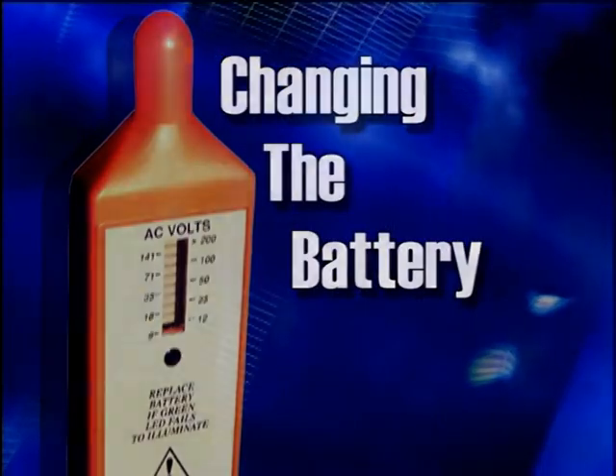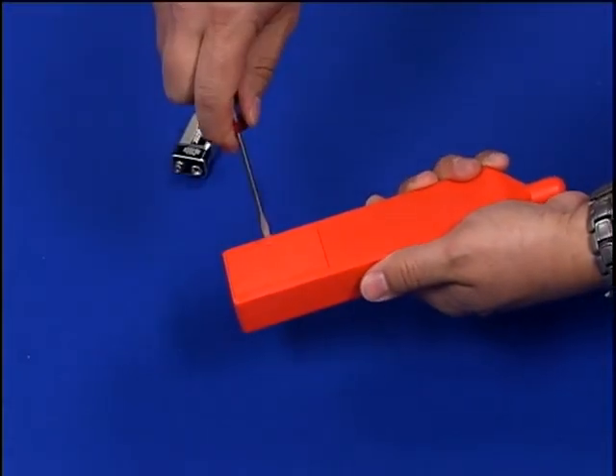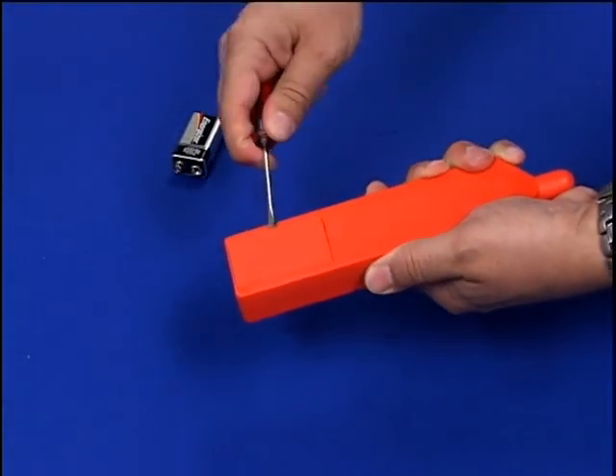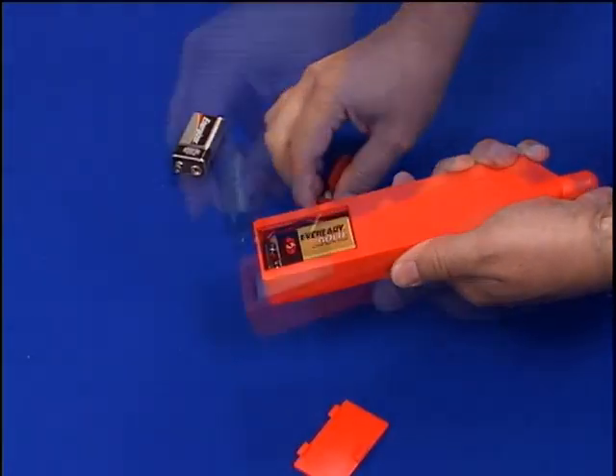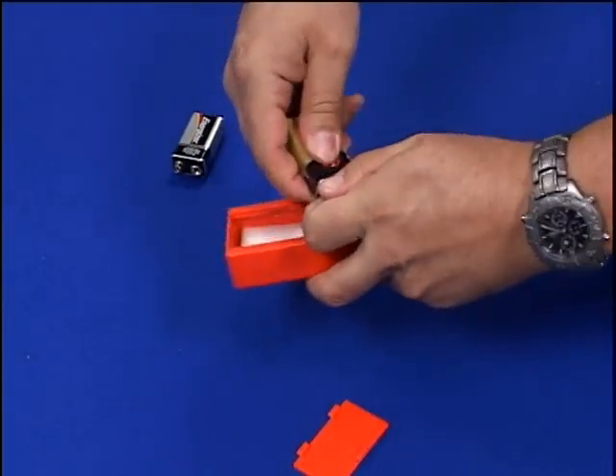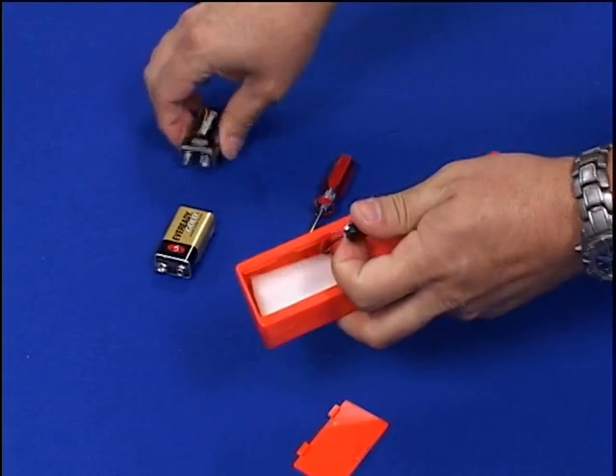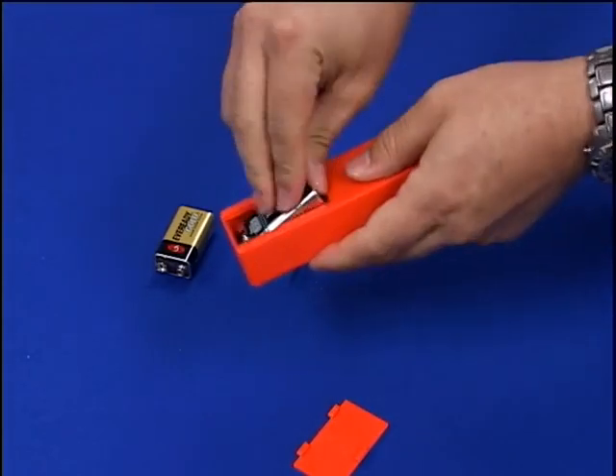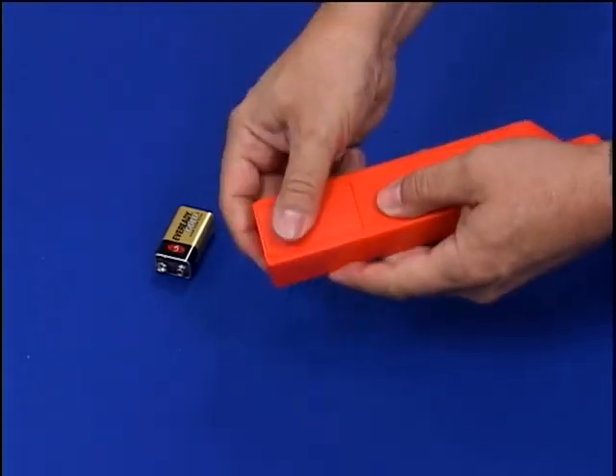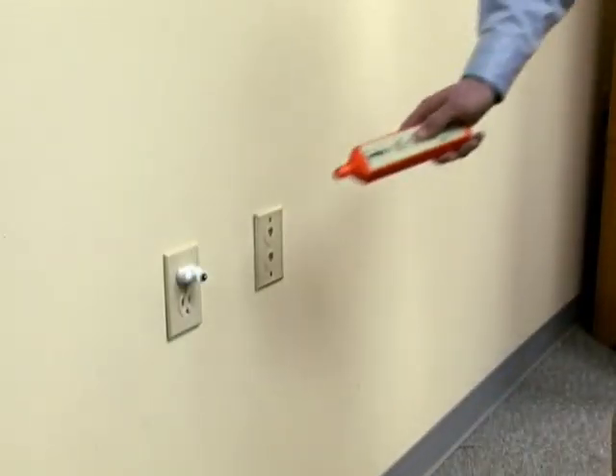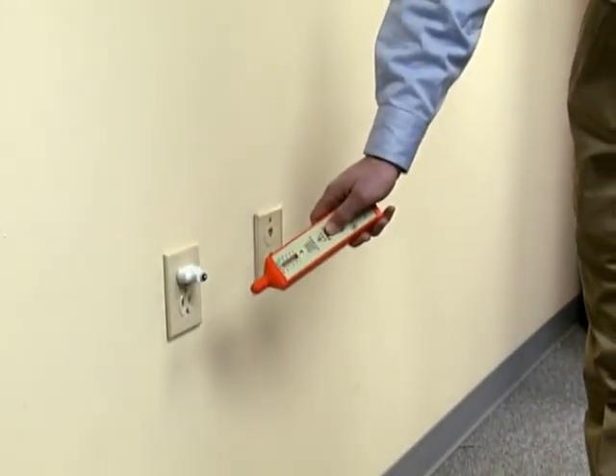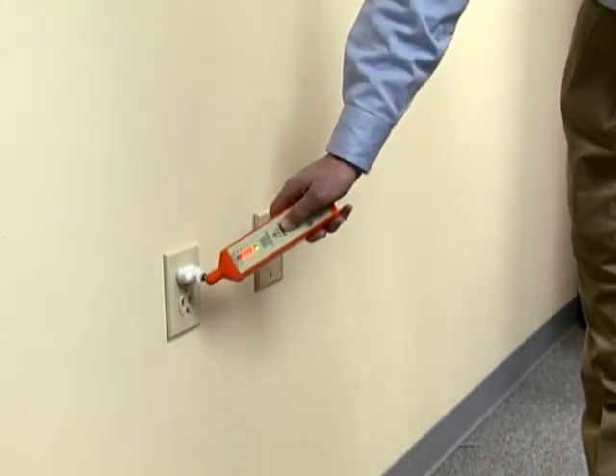To change the battery, first locate the small slot in the battery cover on the back side of the FVD. Using a small screwdriver, simply pry the cover out. Replace the battery with a good quality 9-volt alkaline battery, reinstall the cover, and the FVD is ready to use. Test the FVD on a 193A test plug when you receive it, and then once a month thereafter.